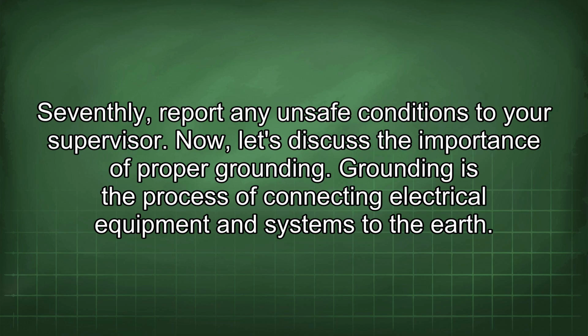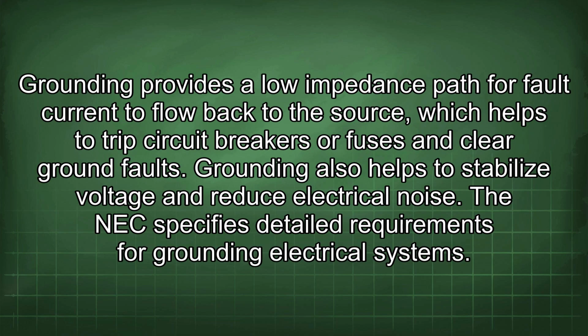Now let's discuss the importance of proper grounding. Grounding is the process of connecting electrical equipment and systems to the earth. Grounding provides a low impedance path for fault current to flow back to the source, which helps to trip circuit breakers or fuses and clear ground faults. Grounding also helps to stabilize voltage and reduce electrical noise.